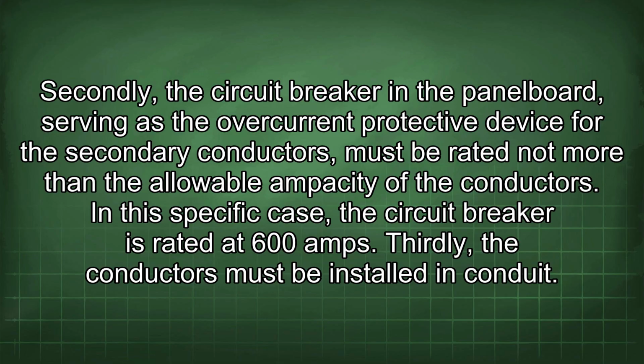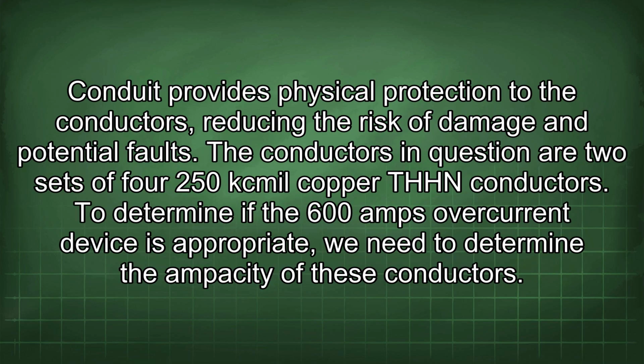Secondly, the circuit breaker in the panel board, serving as the overcurrent protective device for the secondary conductors, must be rated not more than the allowable ampacity of the conductors. In this specific case, the circuit breaker is rated at 600 amps. Thirdly, the conductors must be installed in conduit. Conduit provides physical protection to the conductors, reducing the risk of damage and potential faults.